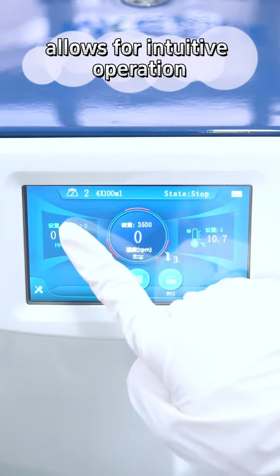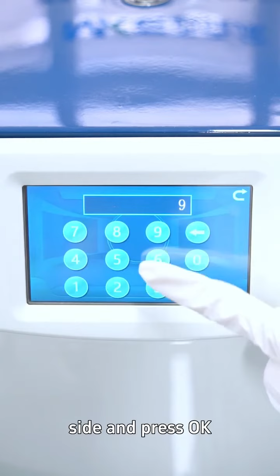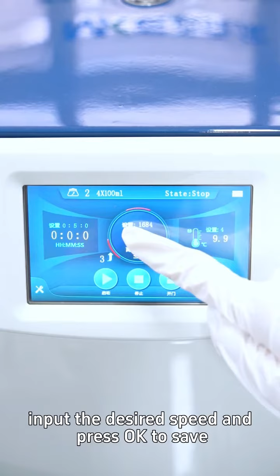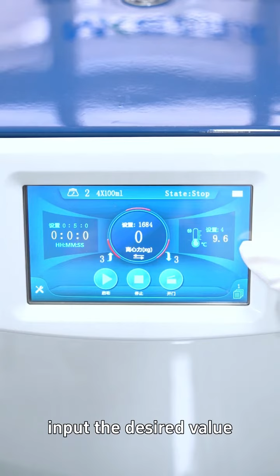To set the centrifuge time, simply input the desired time parameter on the left side and press OK to save. In the middle, the current rotation speed is displayed. Input the desired speed and press OK to save. Press the conversion button at the bottom. It displays the centrifugal force. Similarly, input the desired value. Press OK to save. On the right side is the temperature display.